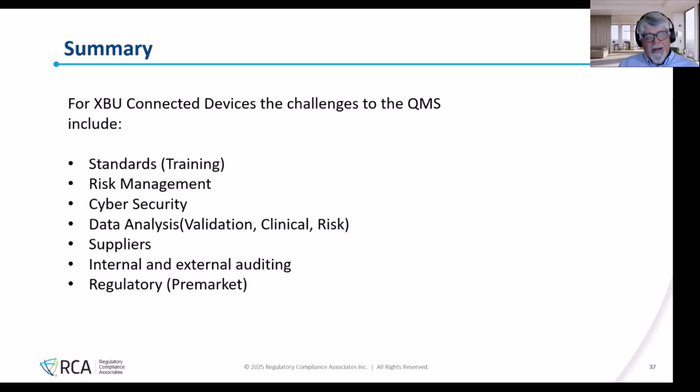You could also be impacted and challenged in the pre-market, getting permission to sell a device in the market, especially if it's a novel device. The route you take could be different. It could be a De Novo, or a 510(k). Most likely it might be a PMA. Those are things you have to worry about. That's why you have to have a regulatory strategy. This concludes the overall fundamental look at the quality management system and some of the processes and regulations that changed.